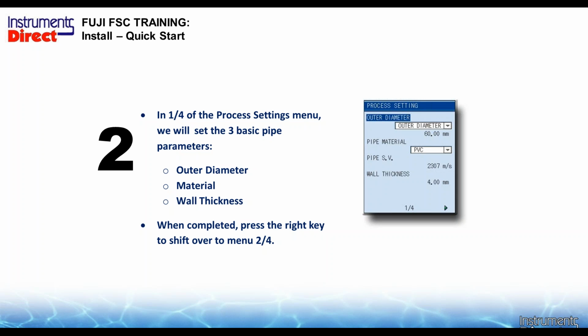So you need to put in the correct outside diameter. So if you're going to say, hey, I got a 3-inch pipe, carbon steel, like a 2x4. 2x4 is not 2x4 anymore. Look in the ANSI pipe chart book and you'll find out that a 3-inch carbon steel OD is 3.5. So here we put in, in this case, you see the picture is millimeters, but if you flip the switch at the beginning, it'd be in English there. Put in the correct pipe OD.